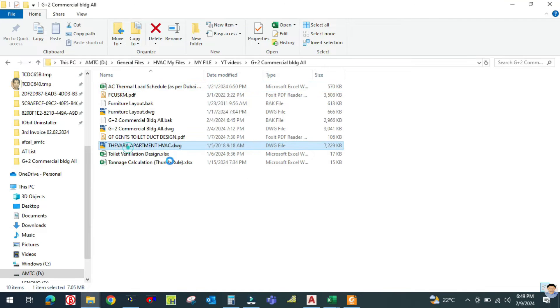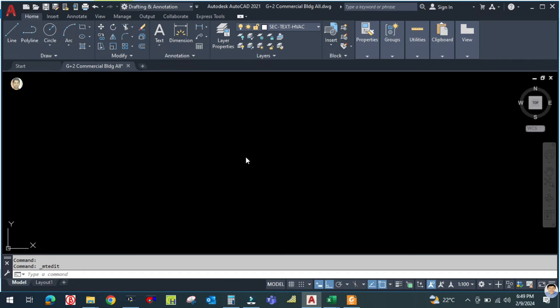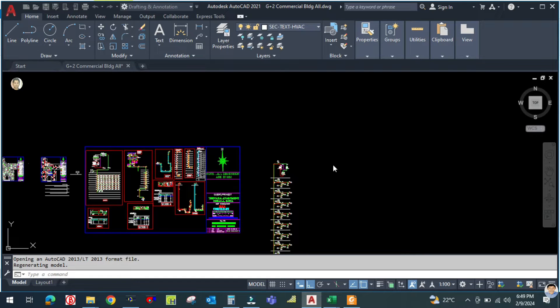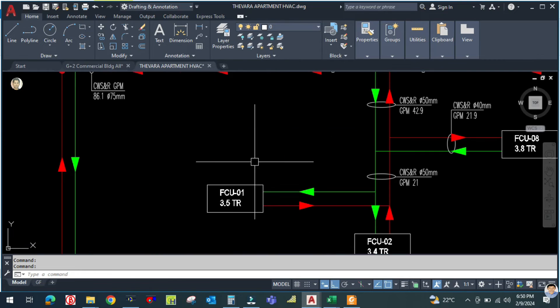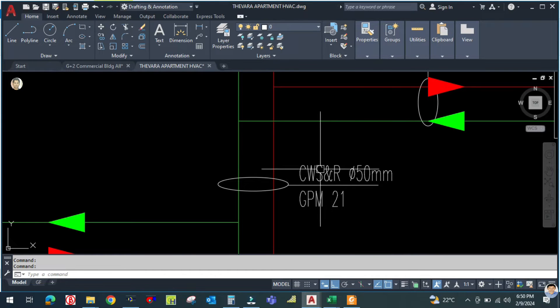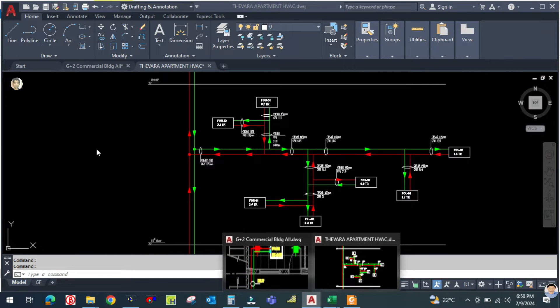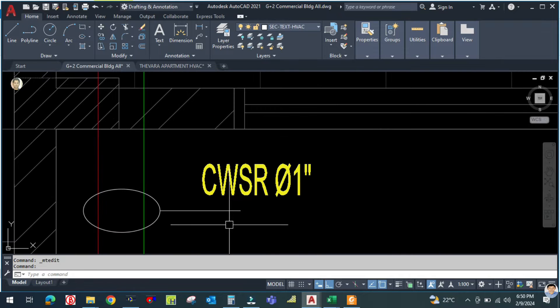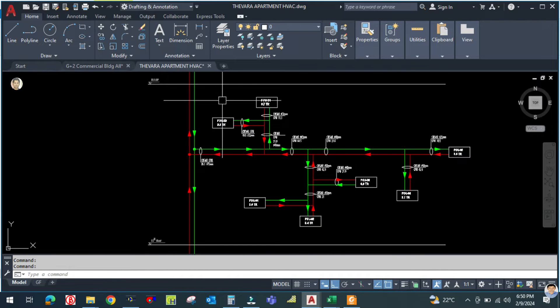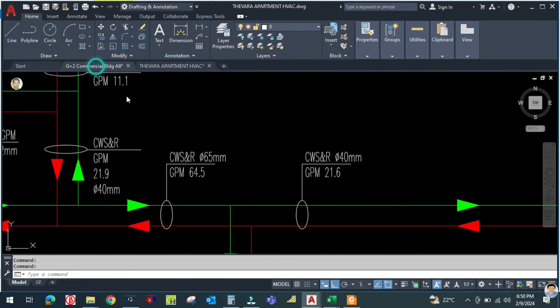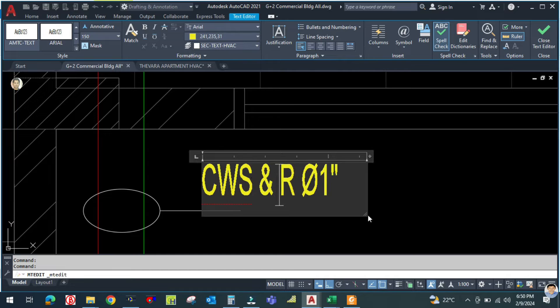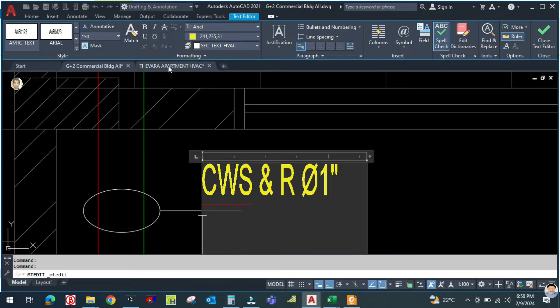Let me open a completed project to show you how the labeling looks. In a completed riser diagram you write: chilled water supply and return (CWS/CWR), diameter, and GPM. So on your project write: CWS and return — dia 1 inch, and below it 7.2 GPM.